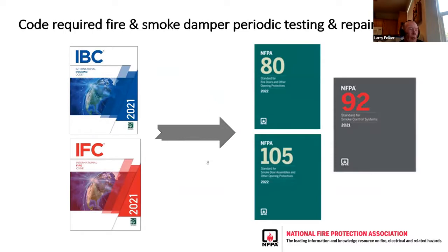UL 555 is a factory standard. Once it's in the field, changes are going to be made. Like any appliance, you're going to repair parts. A damper is considered an appliance, just like a refrigerator. If you change the thermostat in it because it broke, you're not going to find that you have to get recertified. Yeah, that's right. And I think for the most part, it's function over everything. You replace the thing and you need to make sure it functions correctly and fail safe. Yes.